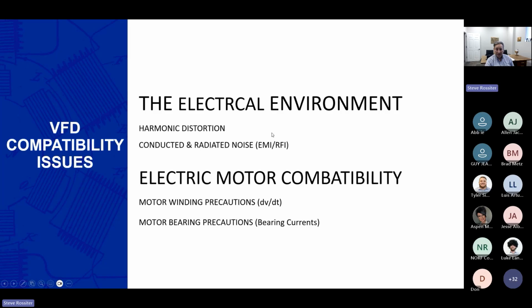So when I think of the electrical environment, harmonic distortion is probably not a term unfamiliar to most of you. That's become a big issue on the electrical grid. And conducted and radiated noise, EMI, RFI, are often referred to as EMC, electromagnetic compatibility, in Europe. There are many standards associated with those. And so that's from the drive feeder side, or the power supply to the drive. We're going to look at those issues, and within the next 15 or 20 minutes, talk about that and specific electric motor compatibility issues like dV/dt precautions on windings and also bearing currents.